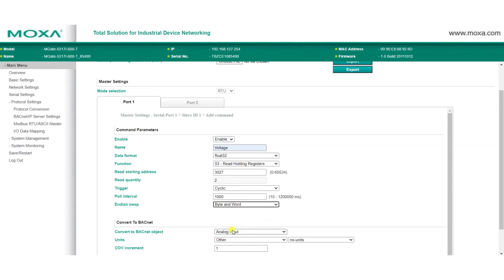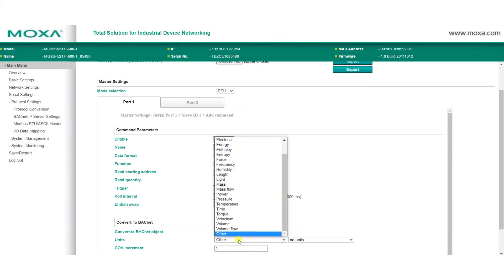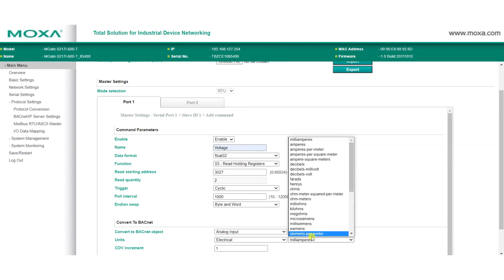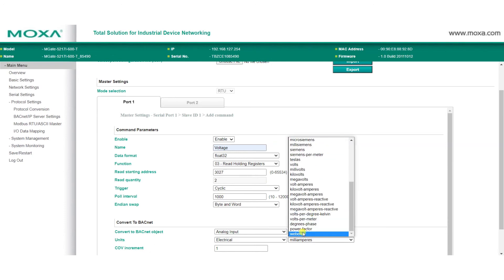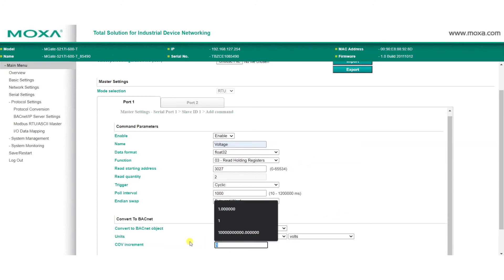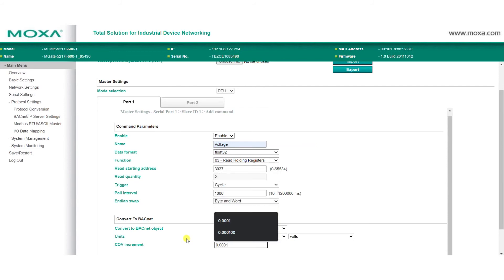Choose the BACnet object type you want to convert to, and set the measuring unit. Here, we're selecting analog input as the object type, and electrical volts as our unit. We'll also set our CoV increments, and then finally, we'll click Done.